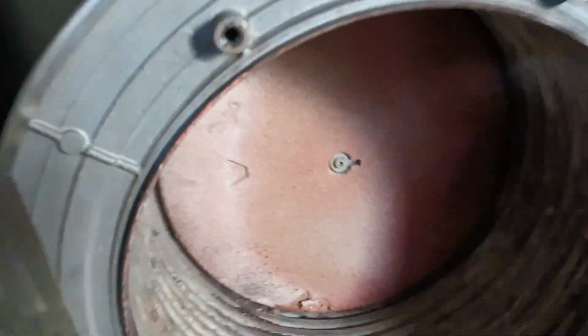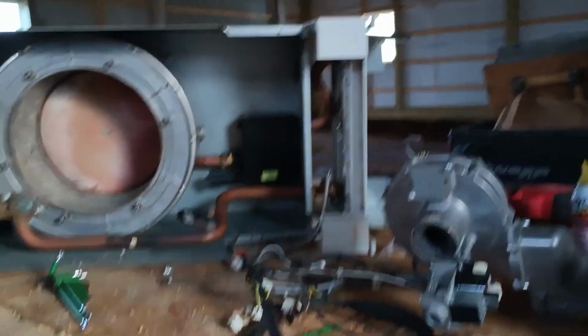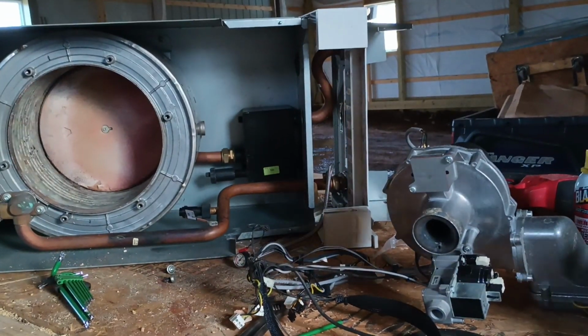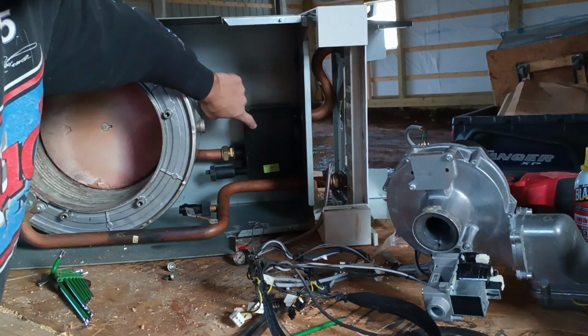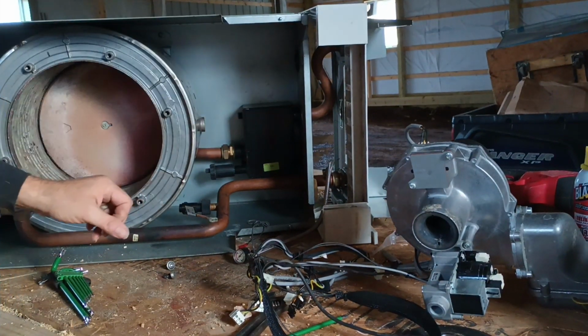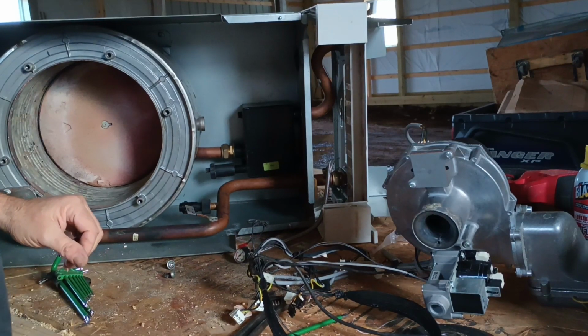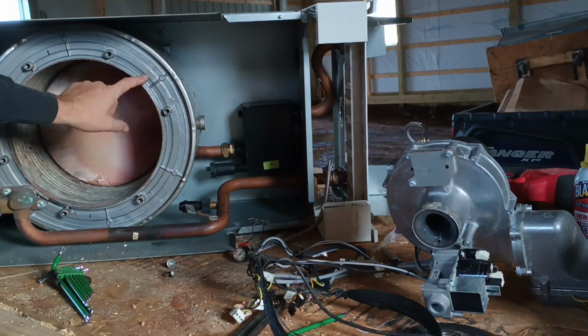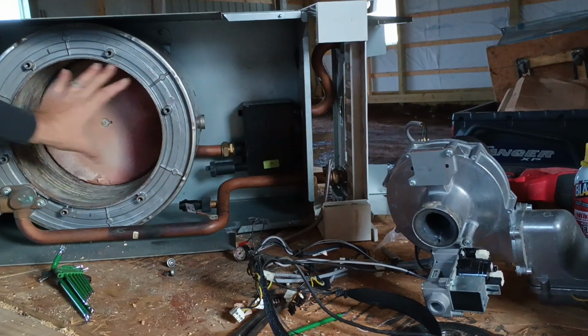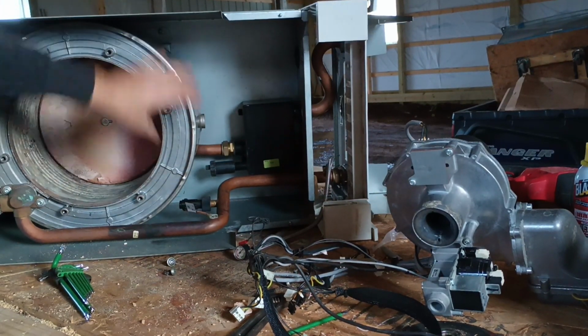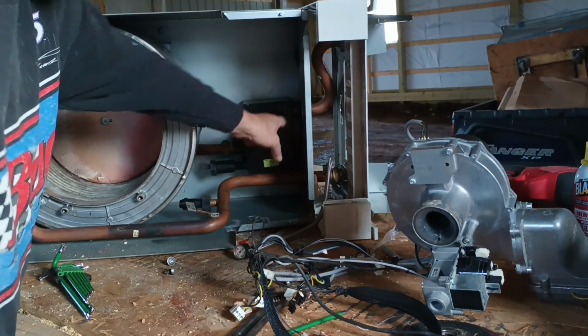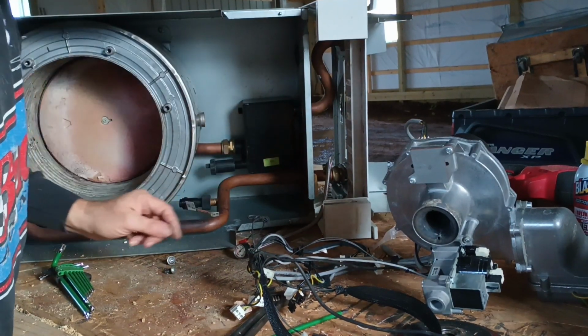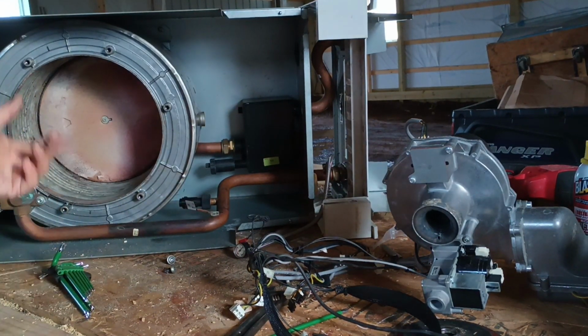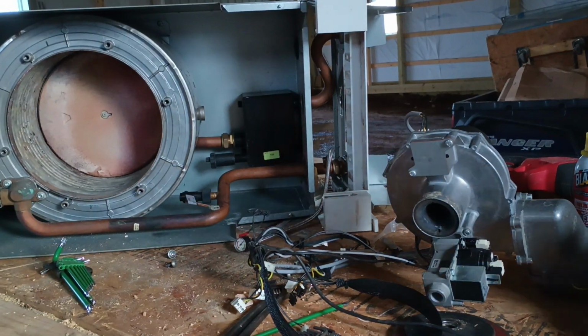Let's pull the back refractory off and throw this back in the camera stand so I can juggle with both hands. I had a contractor calling me earlier today trying to replace this item. Said that he couldn't get it and thought we needed to pull the heat exchanger to get it out. I think in afterthought now, all he really needed to do was just pull the burner off. Then he doesn't have to get into the water side at all. There's a union on the bottom half and a union on the top half. Yeah, you bust those apart and it should come right open.